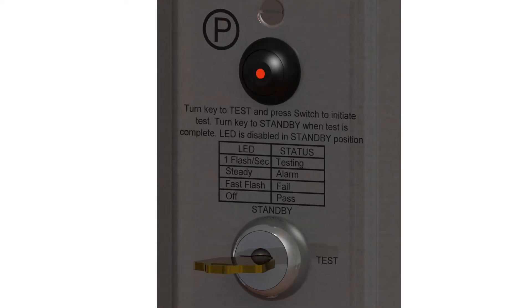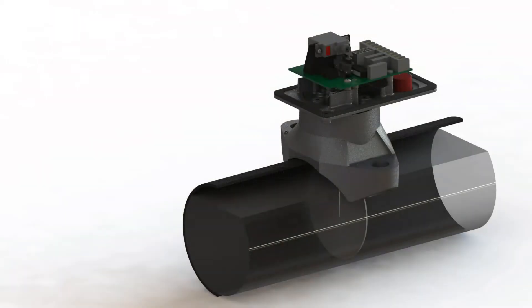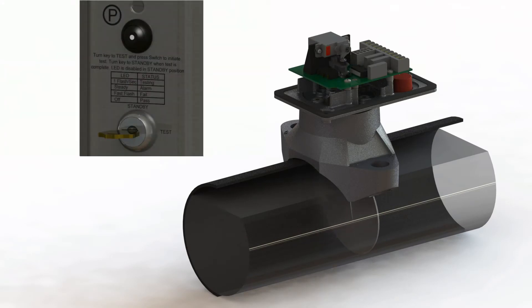This will activate the servo motor which simulates water flow by moving the trip stem on the VSR-AT. The LED on the ATC push button switch will flash once per second as the retard is being timed.